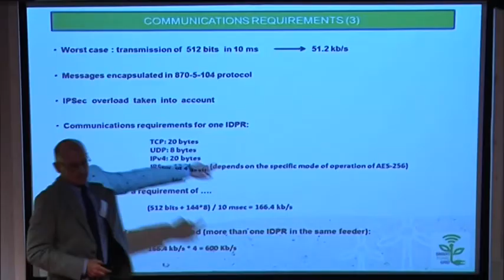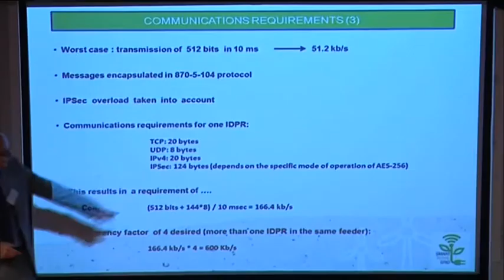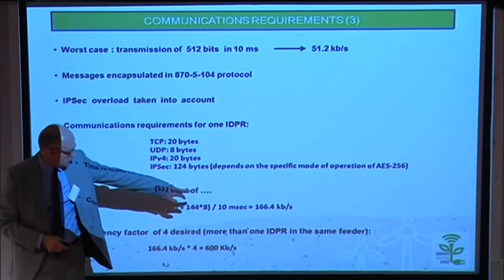But if you remember Ramon's overheads this morning, the IDPR is connected to an RTU that encapsulates all these messages into a 104 protocol. We encapsulate this in a 104 protocol, which means TCP and IP, and also looks like a nice idea to prepare the system for the cybersecurity world - it's a fashionable subject these days. So if I add this 512 bits plus the TCP and IP overhead, that leads to a requirement of 166 kilobits per second.